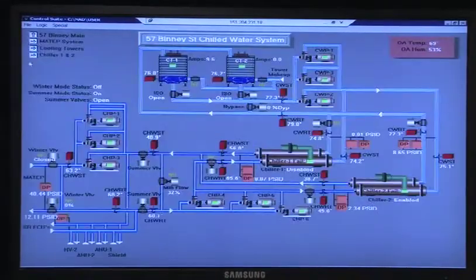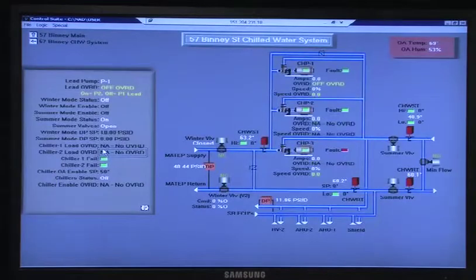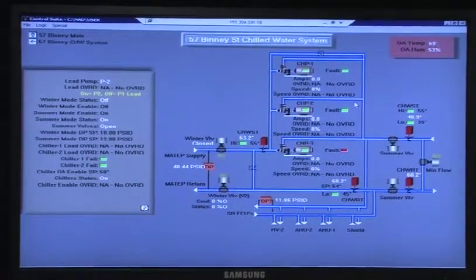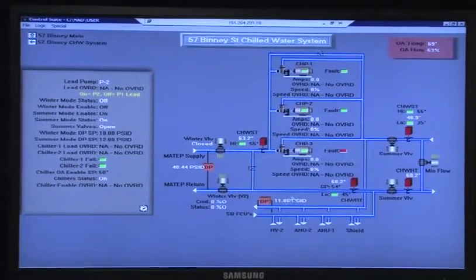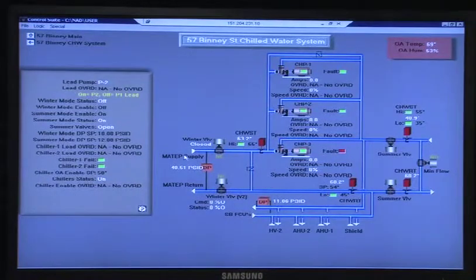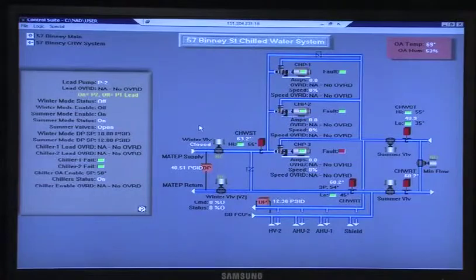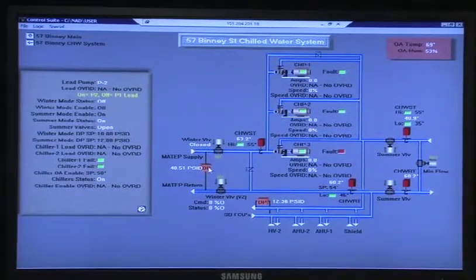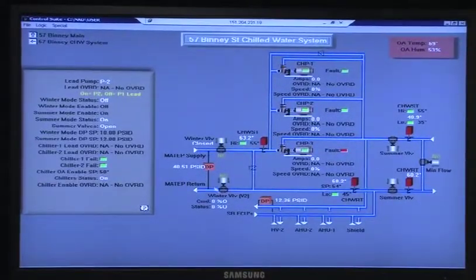All right, so the third section of this: you get the condensing, our chiller plant, and then the third one up here is the MATEP side, and we'll talk about the switchover sections of that, where they cross over. So the MATEP side here is MATEP supply, MATEP return. We all know the MATEP chill water comes into the building in the steam tunnel head, rifles all the way up to the 12th floor. It goes up to the 12th floor of the penthouse, and we come through here. It comes through the side walls.